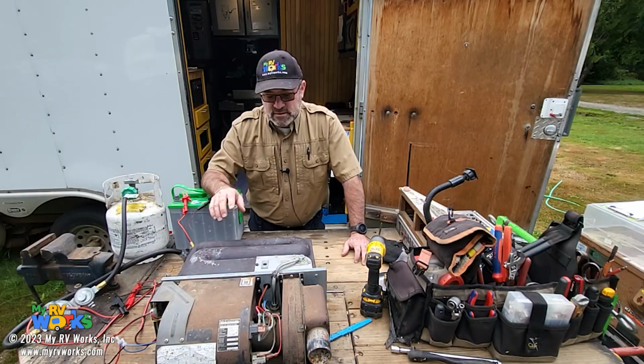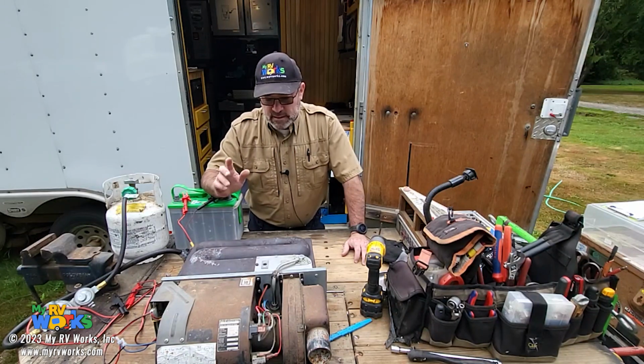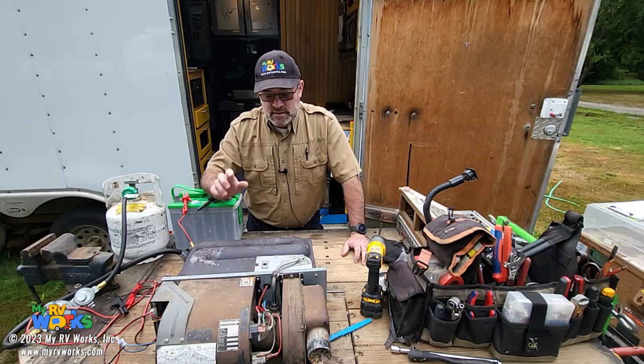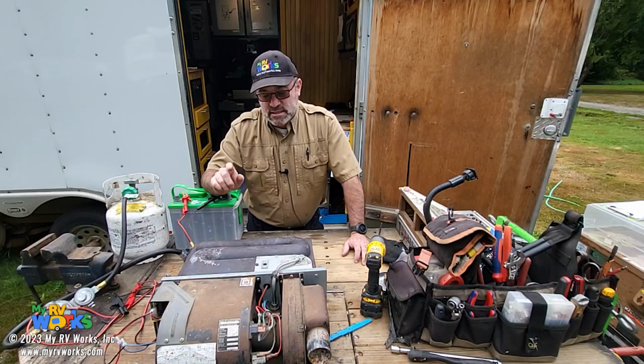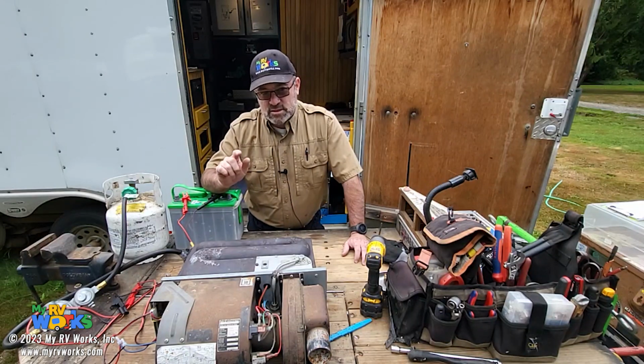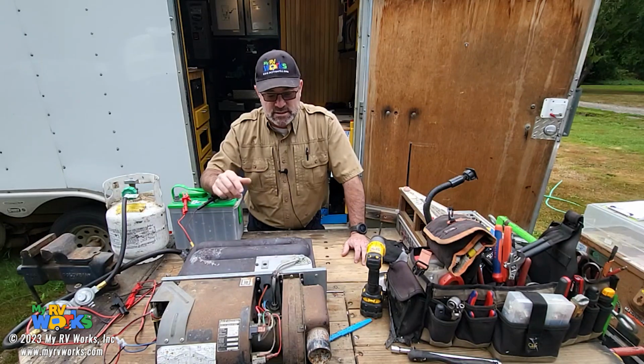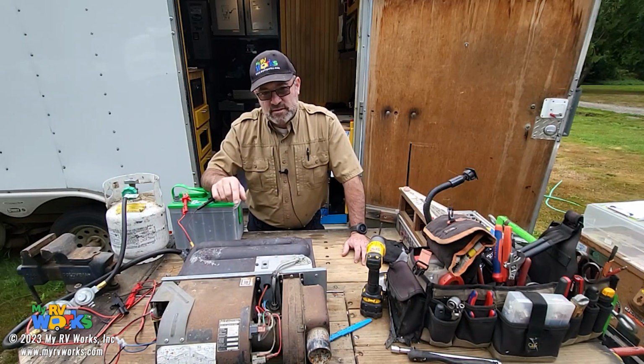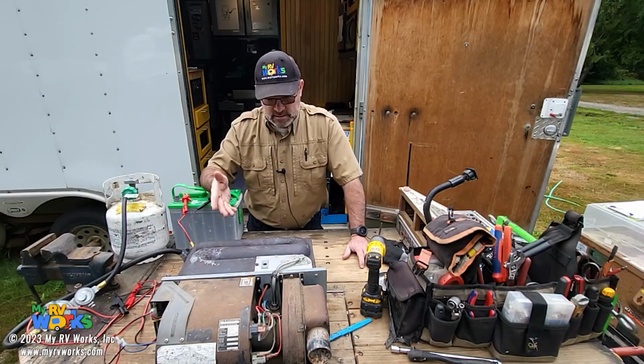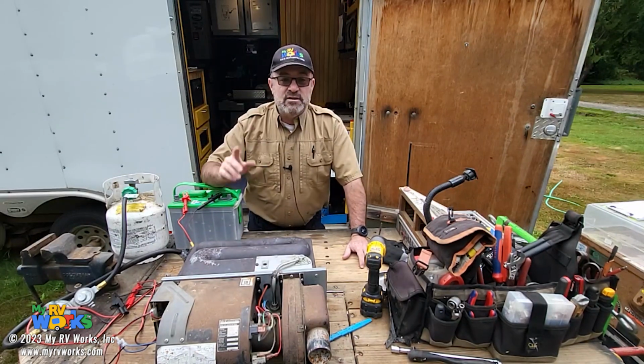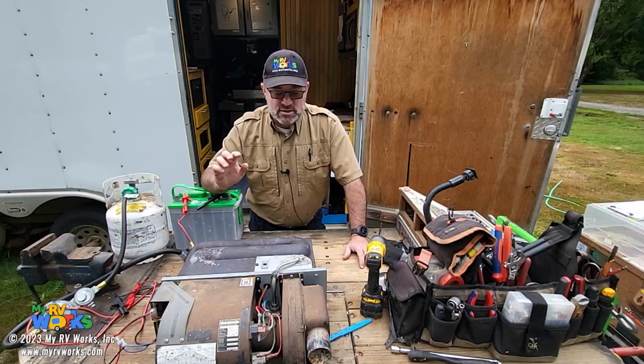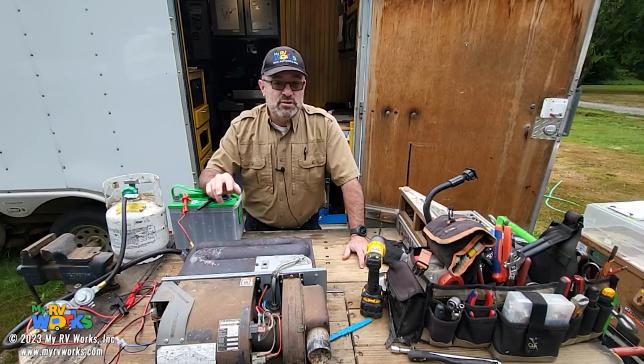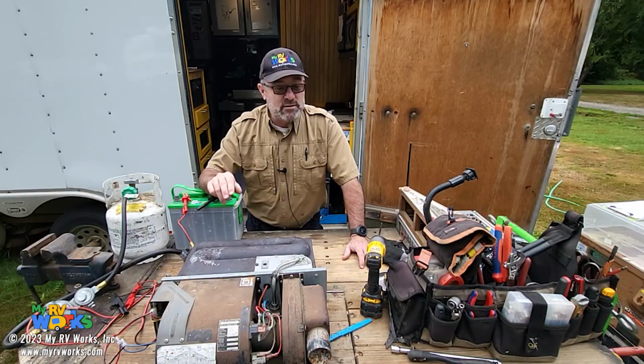Some of you are going to have issues finding the motor. For example, this one is an SF30F. It's not enough to go to the parts counter and say you need a motor for a Suburban SF30F, because they've changed it from, I think, a 2.5 inch to a 3 inch, based on the serial number. So when you get parts for these things, you need to know your model number, in this instance Suburban SF30F, and your serial number. On a Suburban appliance, the first two digits of that serial number are the year of manufacture.